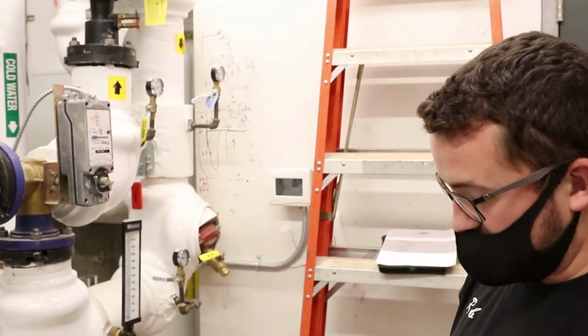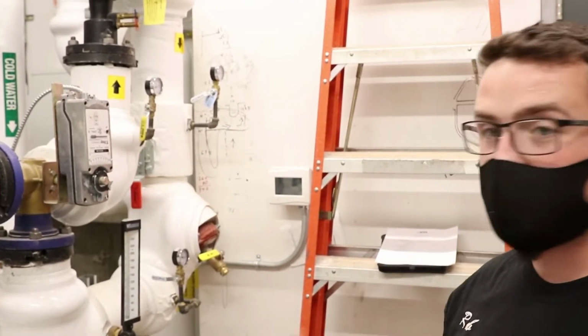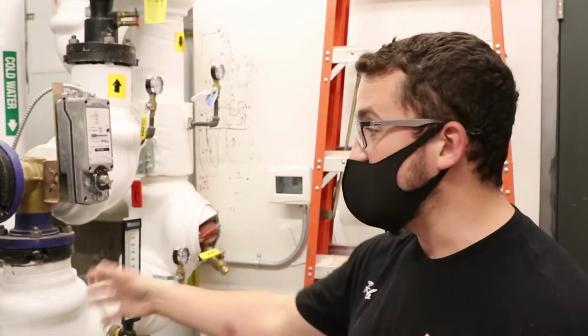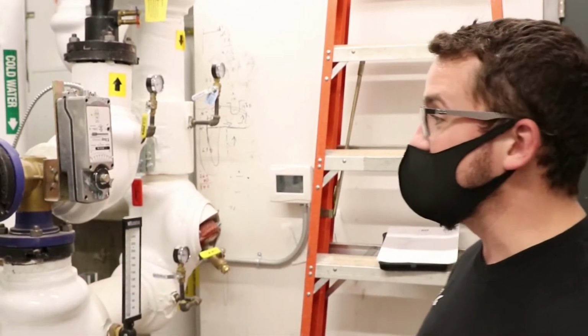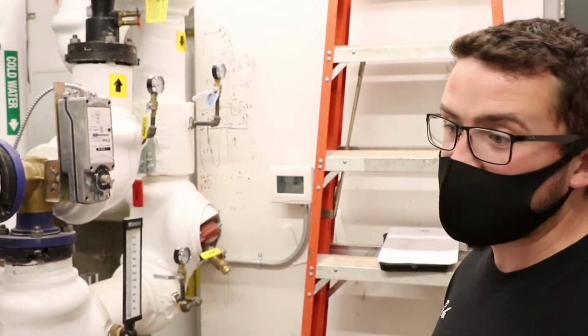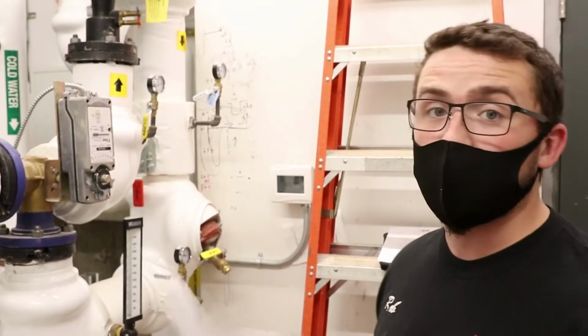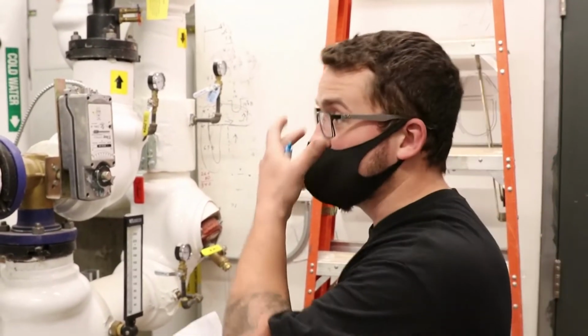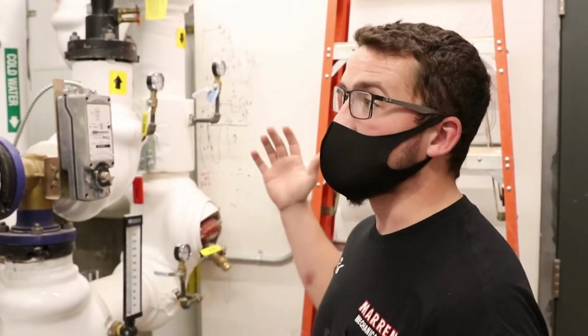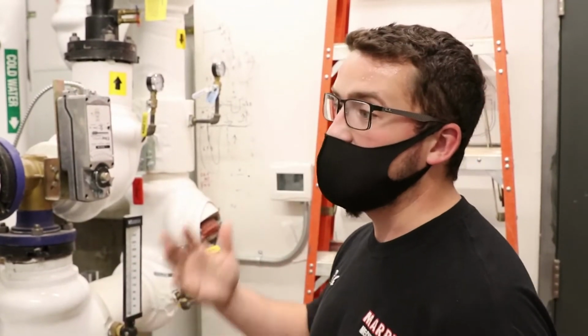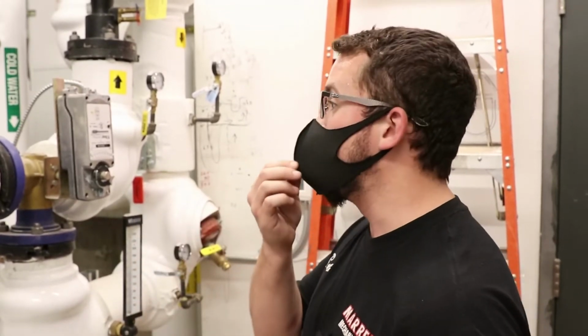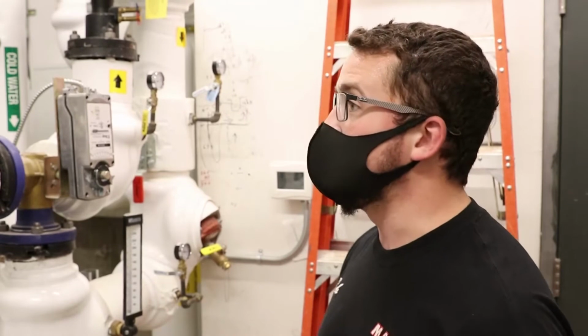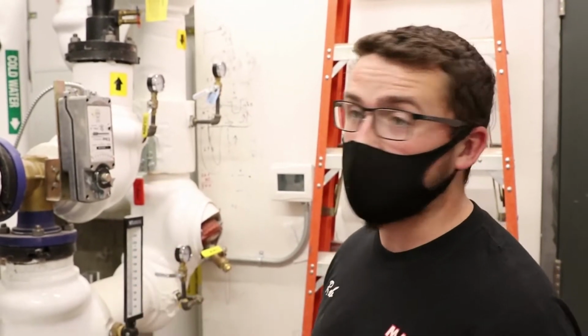As required, flushing and cleaning of the inside of the tank as well as the heat exchanger is done on an as-needed basis, and whether or not this is needed depends on the quality of the water at the site, in addition to how much hot water is being used at the site. The more hot water you use, the more fresh water gets introduced to the tank, the more lime and sediment and things are left behind, and that affects the cleanliness and the efficiency of the heater.